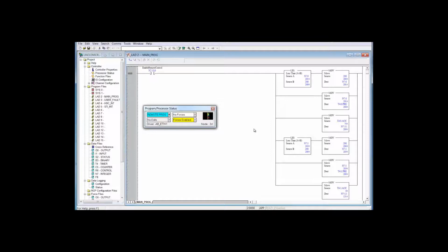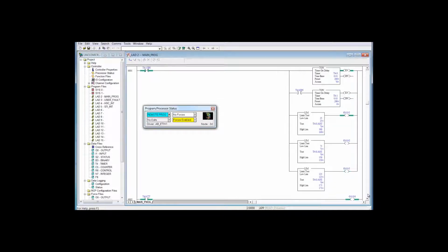Now you see I'm using RSLogix 500 Pro. You might be using MicroStarter Lite and doing this in a 1000, or you could do it in 1100. But looking at the logic that we have, the primary rung is this rung right here. Whenever you see a timer done bit examine off going to a timer, and they're not the same timer data structure, this is T41 and that's T40, then you know that some other timer is controlling the start and reset of this timer.